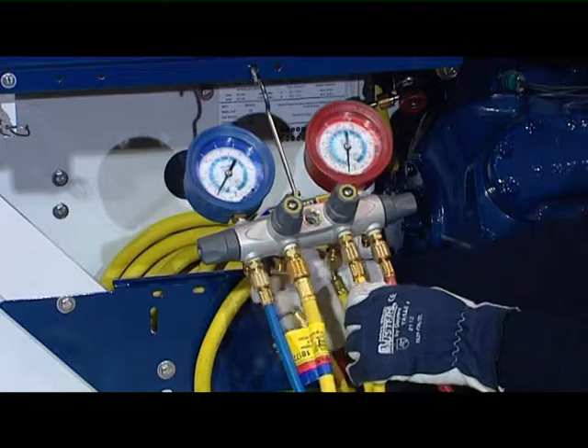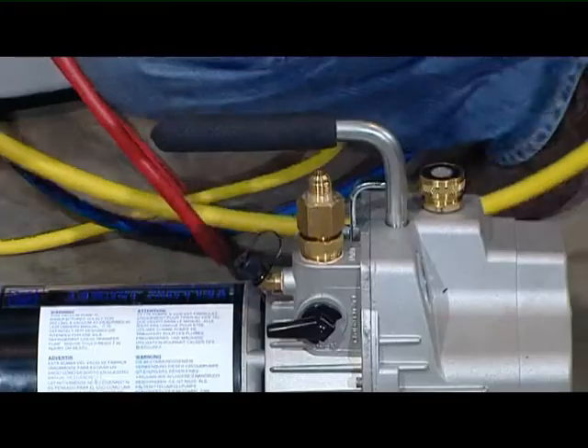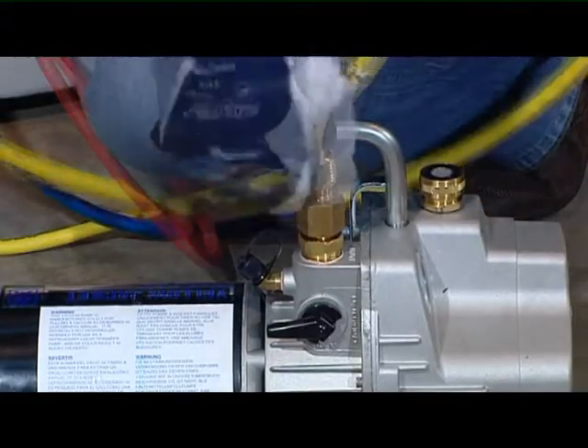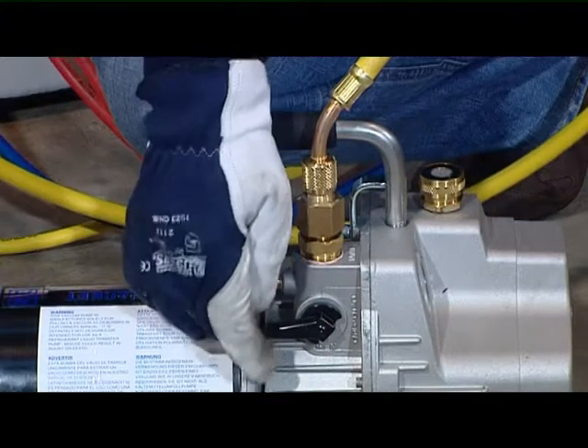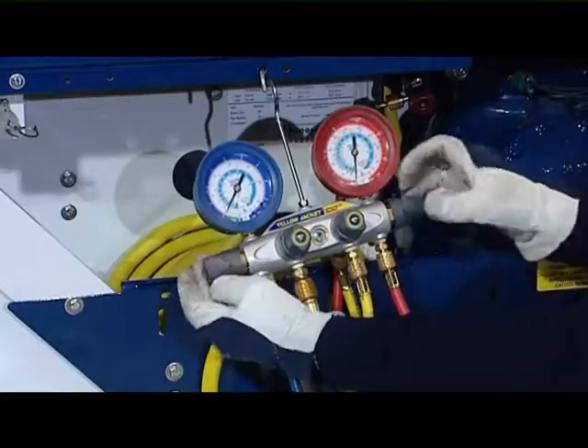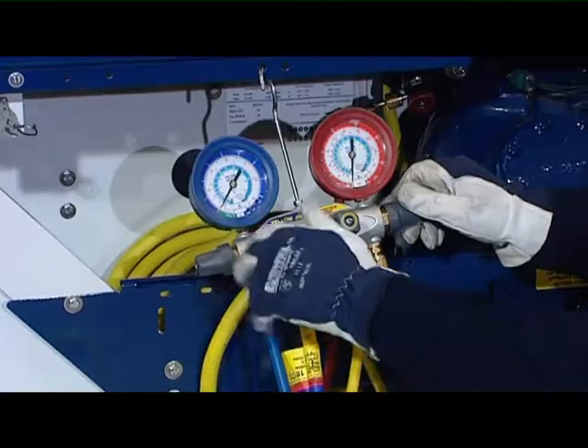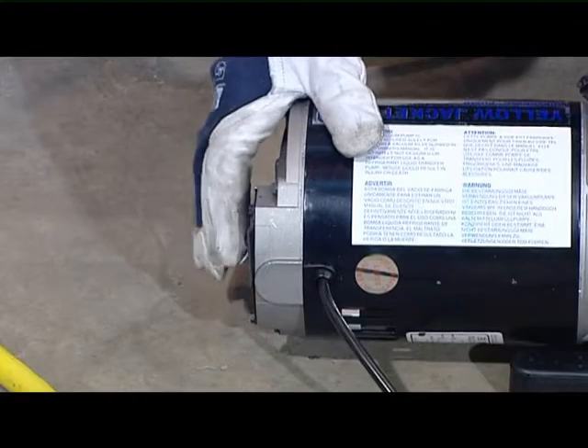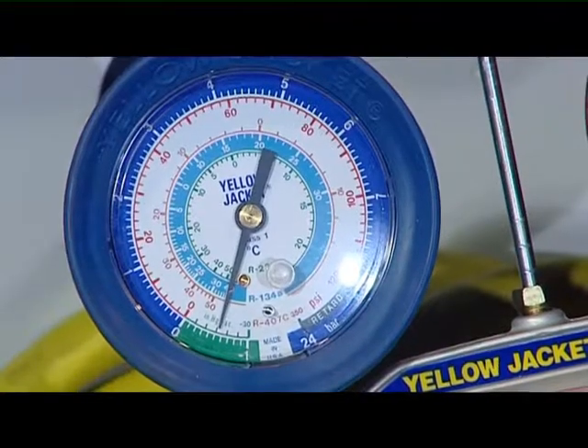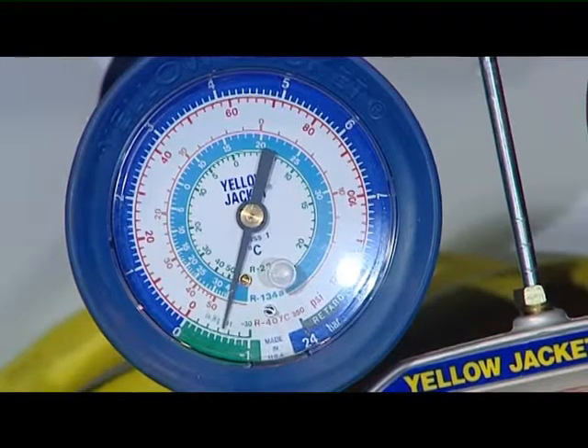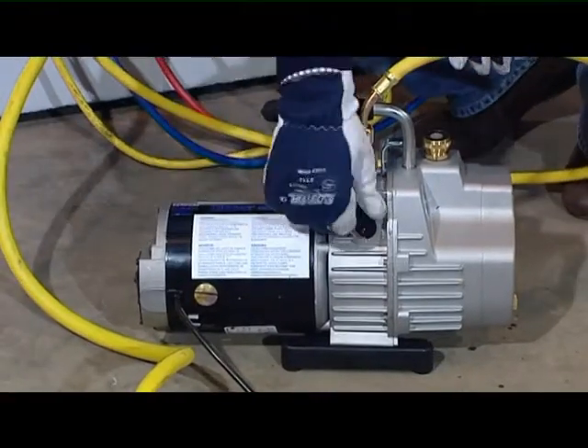Once the TXV valve and filter are replaced, you have to vacuum the system as follows. Connect the big yellow hose to the pump. Open hand valve on the manifold and start vacuum pump. When the system is under vacuum, switch the pump off and close all the hand valves on the manifold.